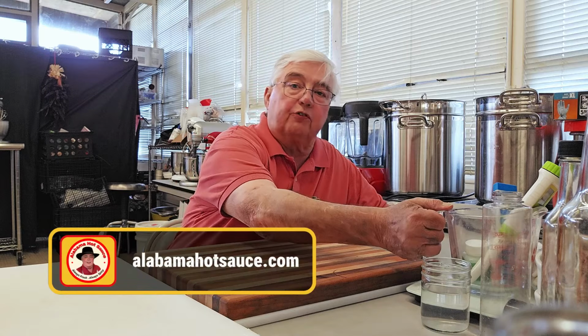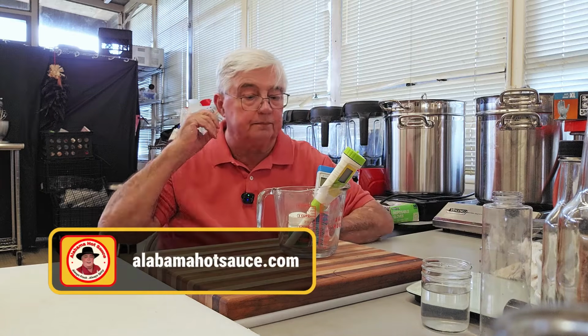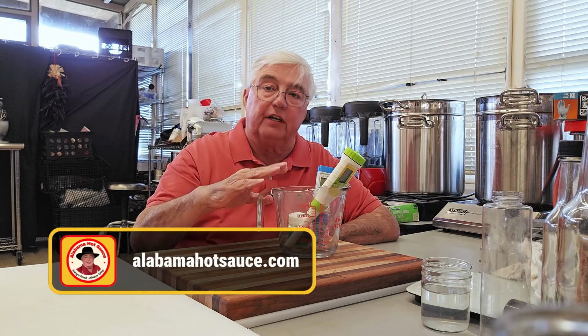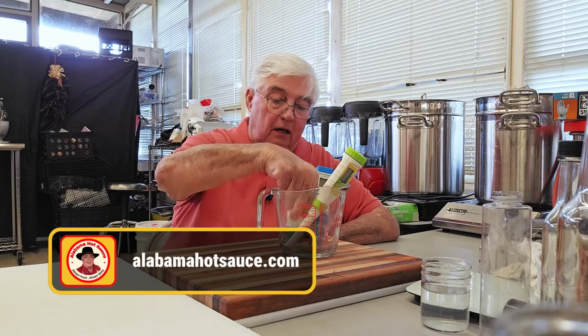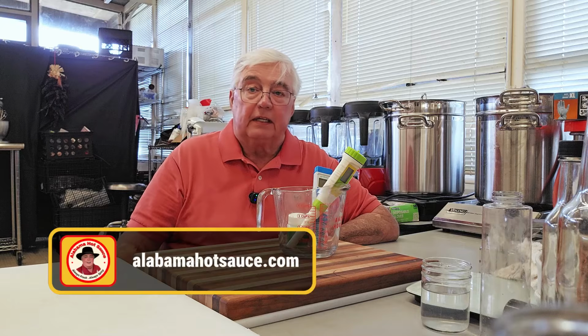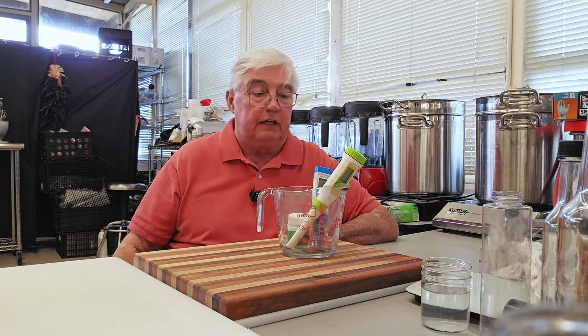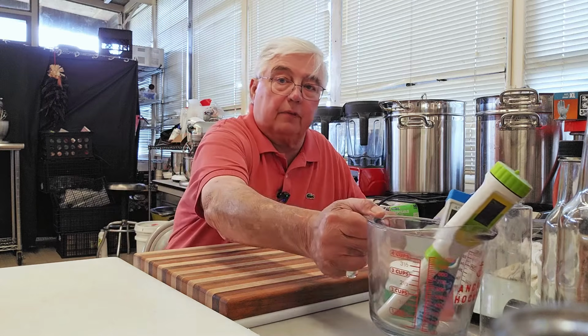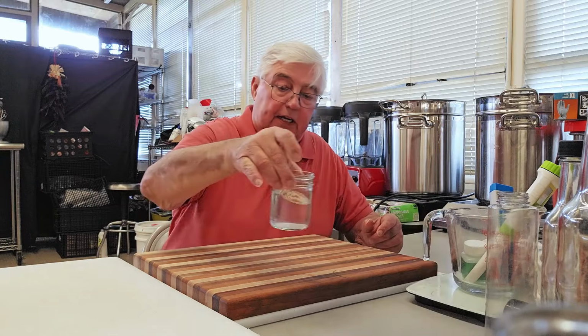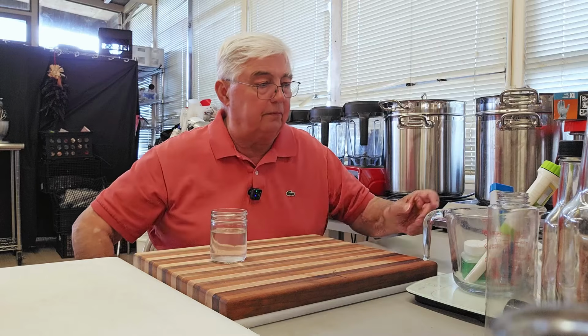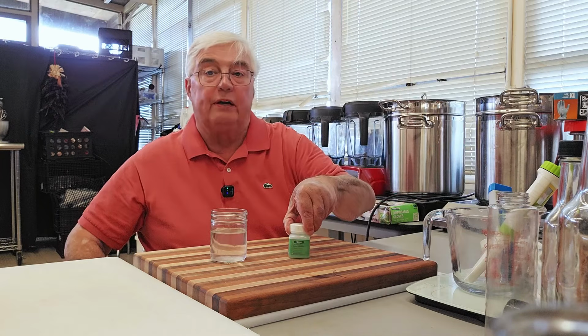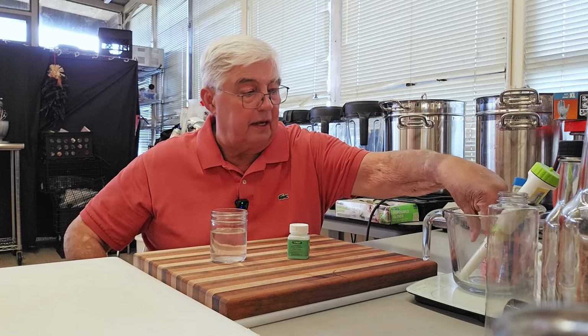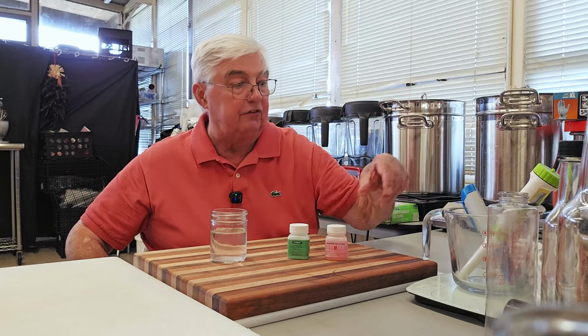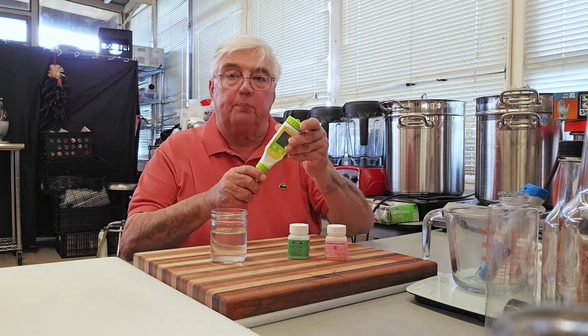First, pH meters are a little more hardy than we give them credit for. I use mine daily. I keep them sitting in a glass measuring cup, just standing up in here. I keep my calibration samples in the measuring cup. I begin the morning by calibrating my meter. I don't necessarily need to calibrate it that often, but I use it so much, and it's so easy, I do it each morning. Now, all you need to calibrate your pH meter is a little container of distilled water, a 7.0 calibration standard and a 4.0 calibration standard. And of course, you need your pH meter.